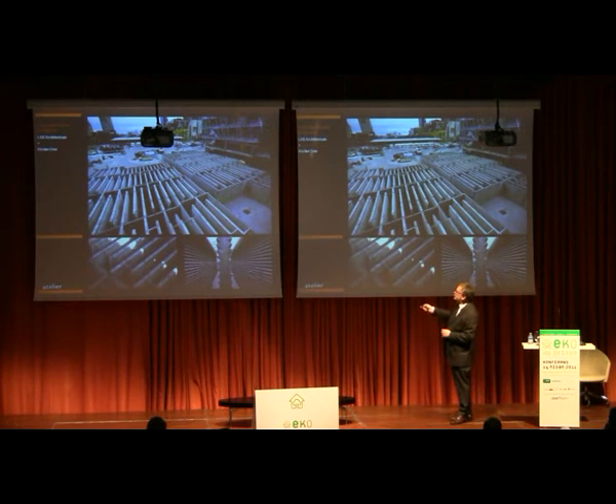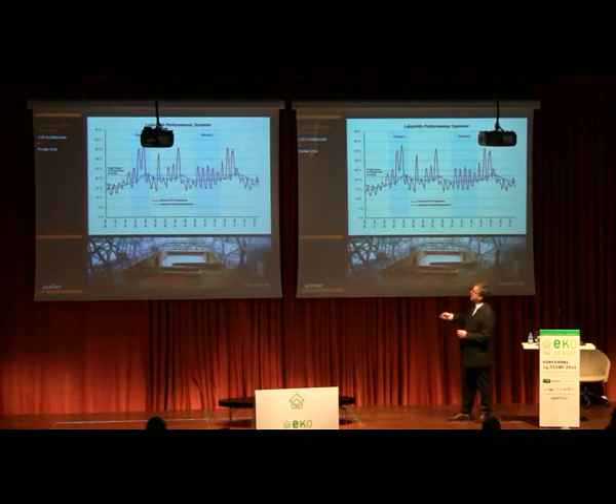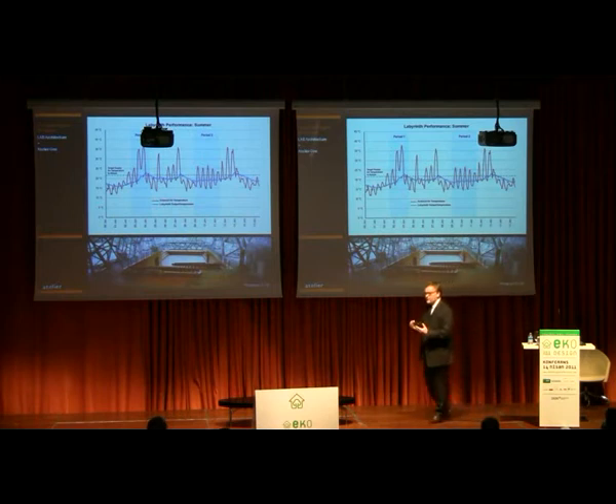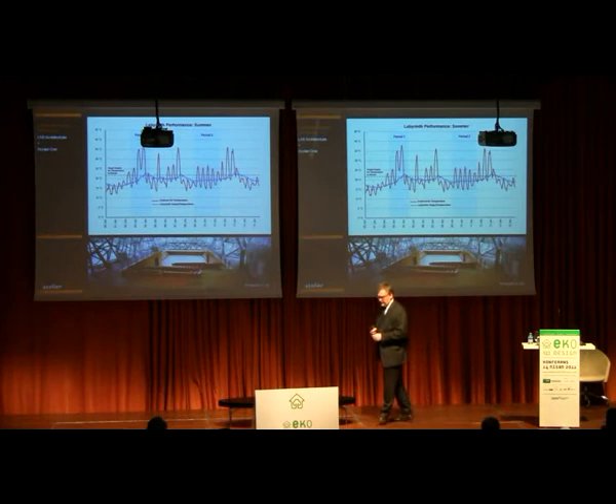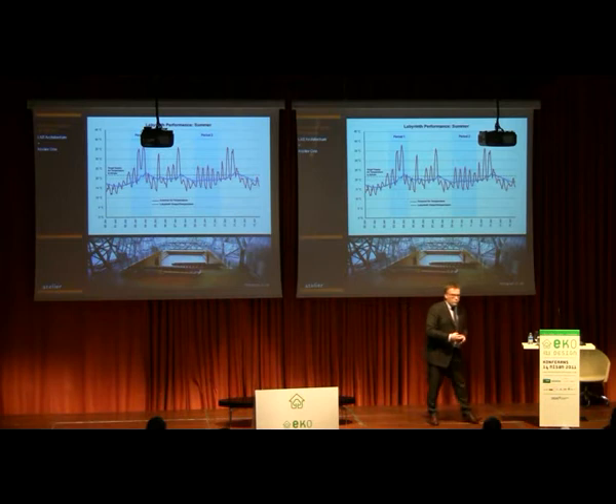So the air passes backwards and forwards, traveling about 250 meters through the labyrinth before it comes out into an air handling unit and gets delivered into the space. In that 250 meters, it cools down from a temperature sometimes up to 43, 44 degrees centigrade to a condition where we can control this atrium space to around 25 degrees centigrade on the hottest day. This has been running for many years and is very successfully keeping the space cool without any refrigeration.